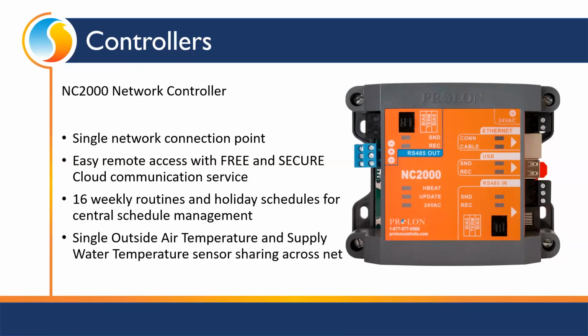You only have one location to go to. So the main office schedule is controlling the 4 units in the main office. When that schedule needs to change, you go change the one schedule, and all 4 of those units follow the new schedule. I had a place I took care of for a while that had 22 independent thermostats throughout the building. I had to walk through twice a year to make sure everything was in sync, and if anybody had fiddled with anything, it would have been much more in their interest to install a system like this to have it all tied back to one location.